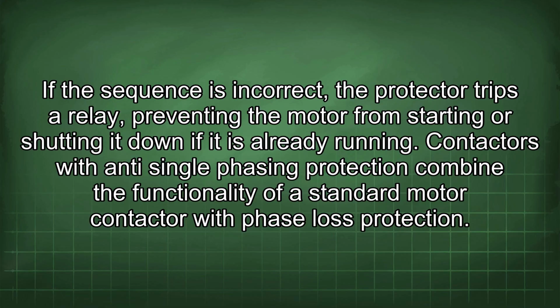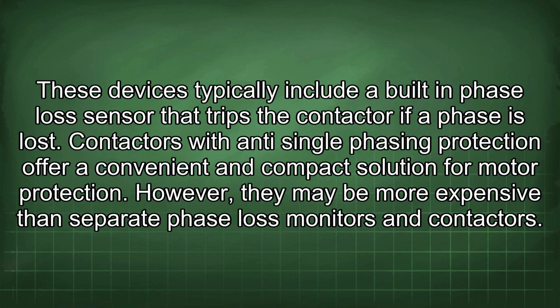it is already running. Contactors with anti-single phasing protection combine the functionality of a standard motor contactor with phase loss protection. These devices typically include a built-in phase loss sensor that trips the contactor if a phase is lost. Contactors with anti-single phasing protection offer a convenient and compact solution for motor protection. However, they may be more expensive than separate phase loss monitors and contactors.